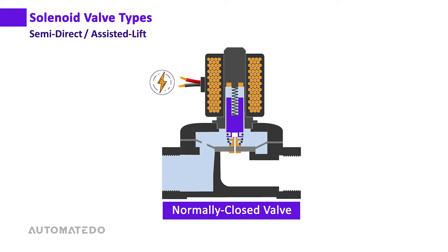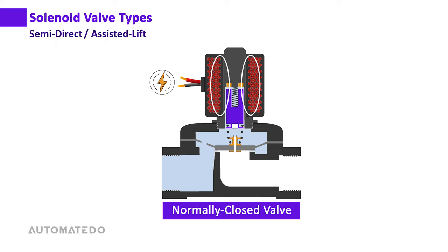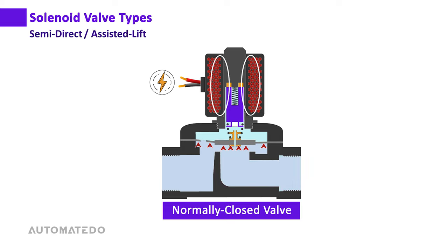When the solenoid energizes, an electromagnetic field is generated which moves the plunger upwards. As the plunger lifts, it also raises the diaphragm and simultaneously opens the orifice, connecting the upper chamber to the outlet. This reduces pressure in the upper chamber, and the diaphragm is now lifted by both the plunger and the resulting pressure differential.